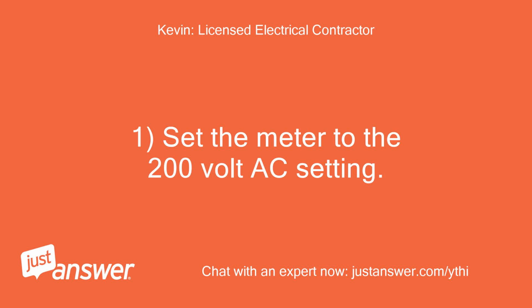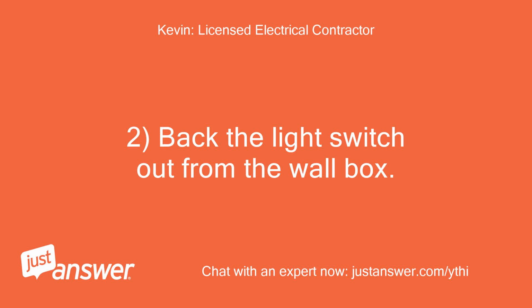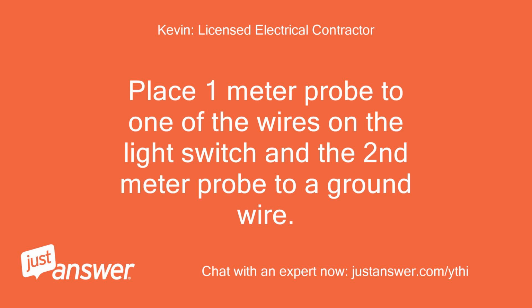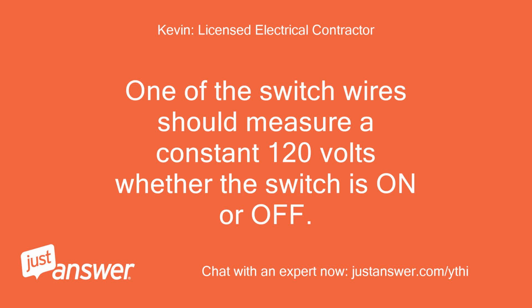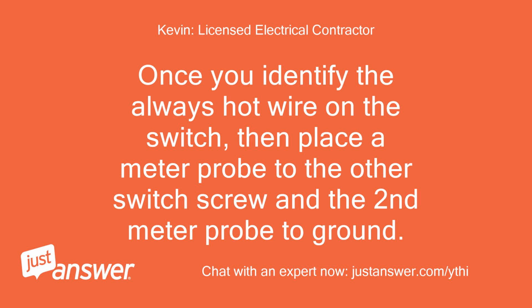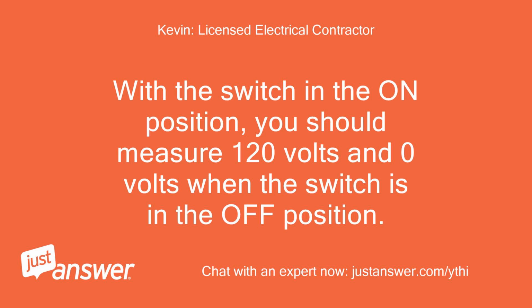1. Set the meter to the 200 volt AC setting. 2. Back the light switch out from the wall box. Place 1 meter probe to one of the wires on the light switch and the second meter probe to a ground wire. One of the switch wires should measure a constant 120 volts whether the switch is on or off. Once you identify the always hot wire on the switch, then place a meter probe to the other switch screw and the second meter probe to ground. With the switch in the on position, you should measure 120 volts and 0 volts when the switch is in the off position.